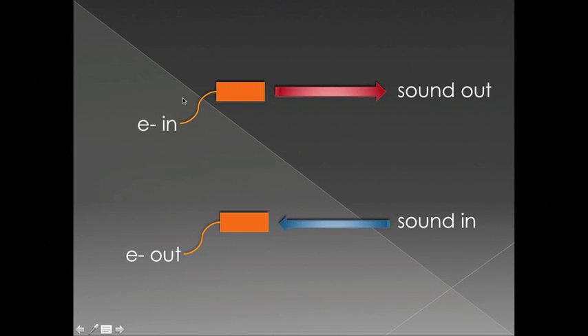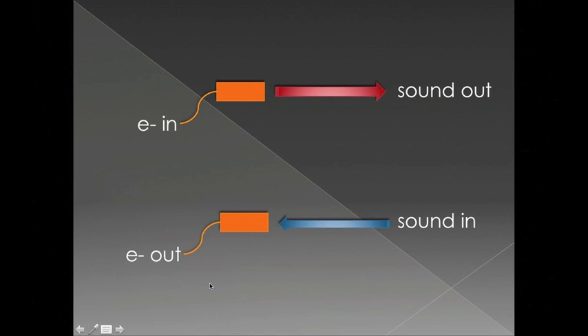So this is the most basic element of any ultrasound transducer: one crystal that sends out sound when it has an electrical current applied to it, and then when a sound wave comes back and hits the crystal again, it produces another electrical current.